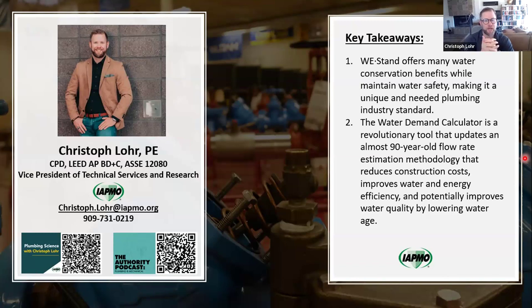That's a great question, Adam. One thing worth noting is that if you start going to submetering, it has the potential to actually increase the amount of piping in your system. Especially in high rise, we tend to like vertical distribution from an engineering standpoint, because you can have the pipes right behind the stacked fixtures from floor to floor. So from a bulk system, particularly chapter four that I mentioned, it's almost going to drive towards an ultrasonic flow meter, which many of the manufacturers are producing.